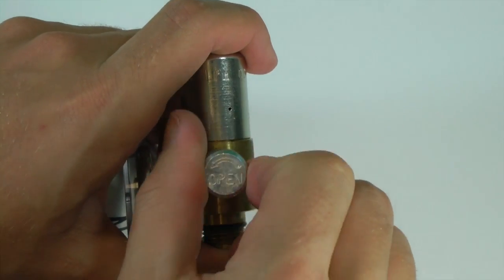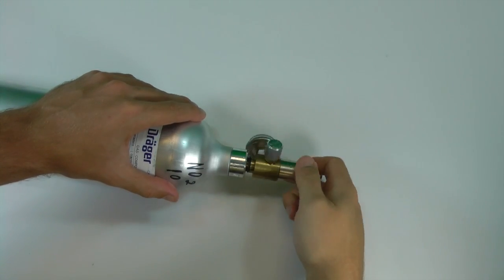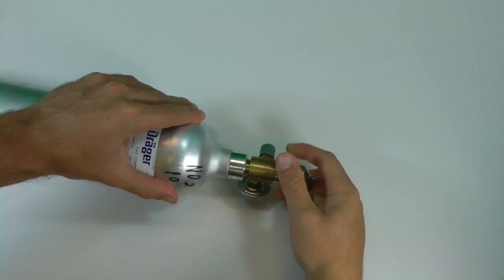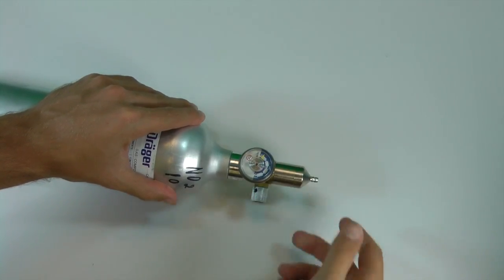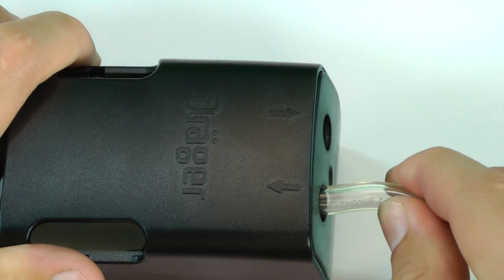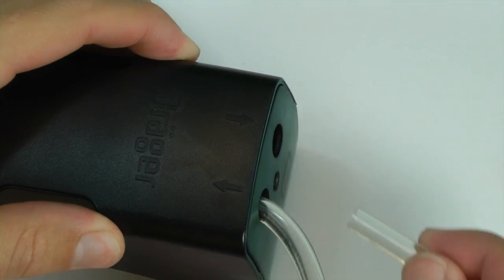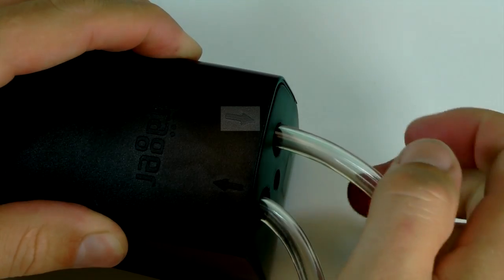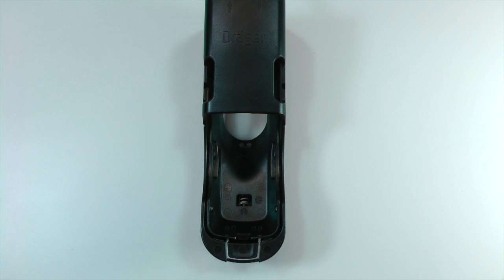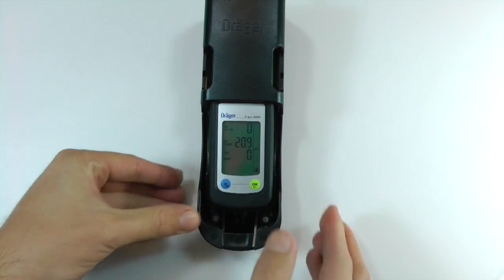Ensure that the calibration gas regulator is closed and then attach the regulator to the appropriate cylinder of calibration gas. Insert the tubing over the regulator and connect the other end to the inlet port towards the instrument on the calibration cradle. You can connect another piece of tubing to the outlet port on the cradle and direct the other end into a fume hood. Insert the instrument into the calibration cradle. You should hear a click once the instrument is secured.